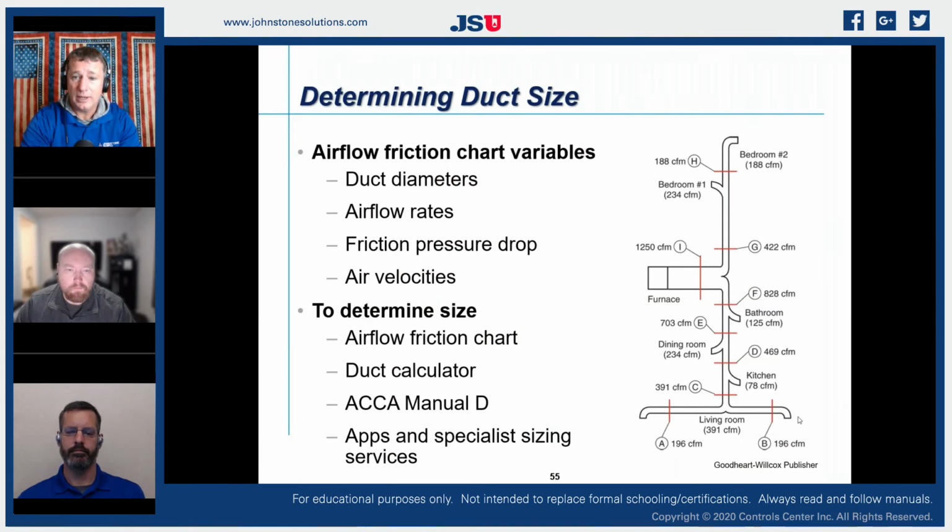So that gets us all the way down the straightaway. So on that particular section, we're now going to have an 8x12 trunk that's going to supply an 8-inch register at bedroom 2. Just after that, I'm now going to do a transition down to an 8x8. So we're going to use a standard tapered transition right here.